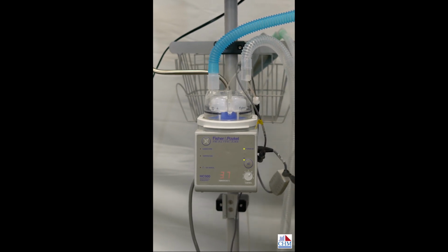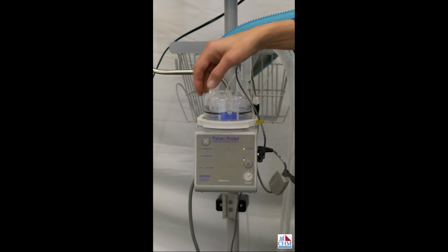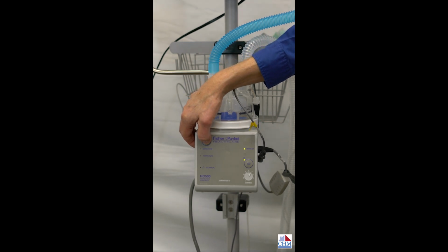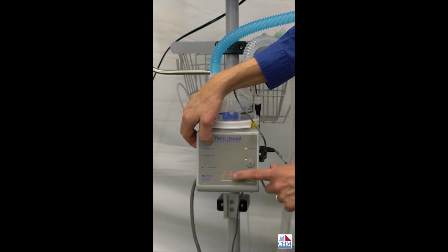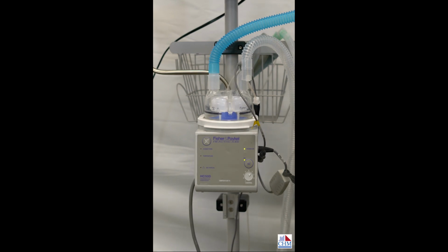We've got a couple of alarms on the machine if we do have trouble, and there's an alarm silence button right here. That alarm silence button will also show us, if we push on it, the current temperature that the unit is sensing proximal to the patient. Right now, of course, it's not coming up. We don't have water in it, and the Trilogy is not on and running, so it's just sitting down at 23. But that's the operation. The alarms that we can get on it are connector and temperature. There's just those two categories.